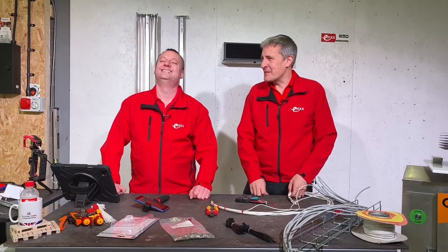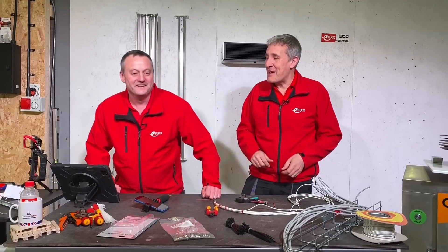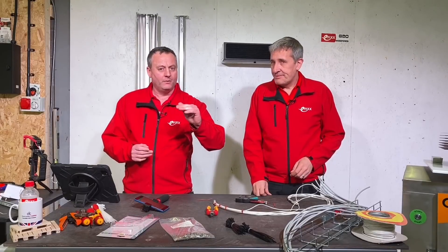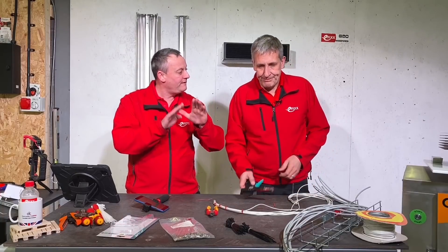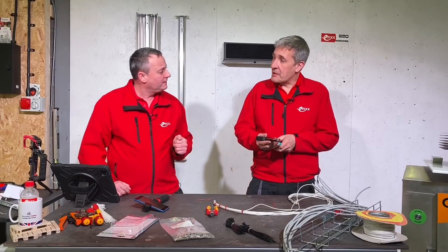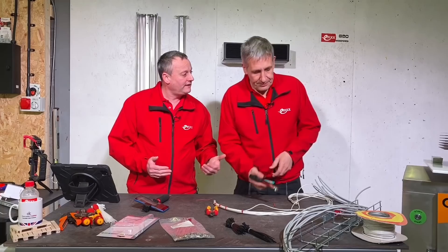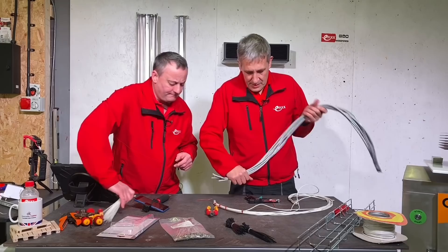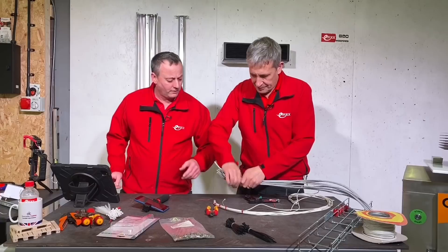I bet that guy we met in Doncaster last year, who did an impressive result on the challenge wall - he's ripping cable ties to bits every day. And so when you start pulling it tighter and tighter and tighter, you actually start denting and reforming the cables you're trying to support to a basket. So you're saying you can go too far - you can, and you look at the effect on the actual conductors themselves. So we're going to take these white ones, set at three kg of tensile strength.